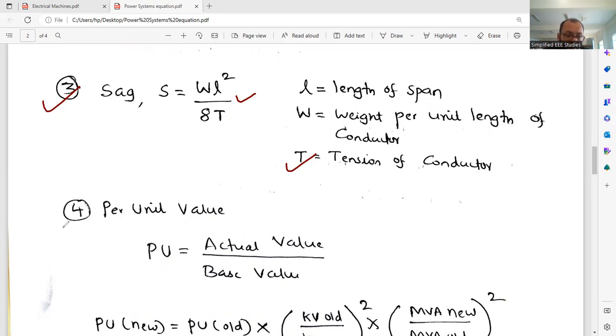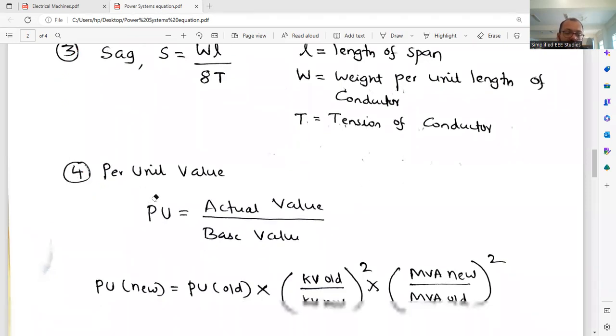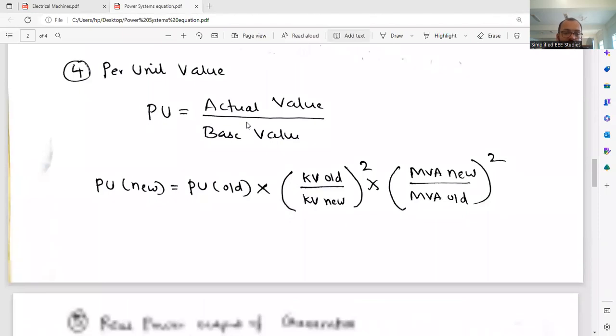All right. Next is per unit value: actual value by base value. The per unit value is also very important. What is per unit value? Similarly, you can expect one numerical example using the formula. The new per unit value can be calculated using the formula: PU old multiplied by (KV old by KV new) the whole square, into (MVA new by MVA old). This is very, very important. So kindly make a note of this.